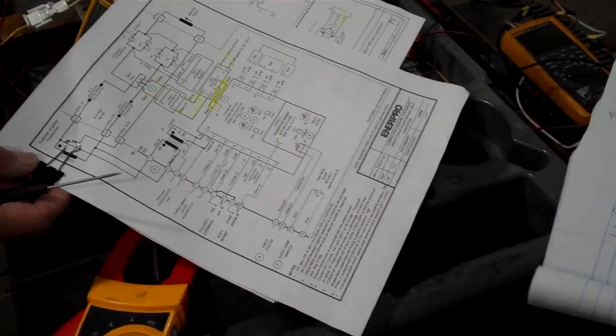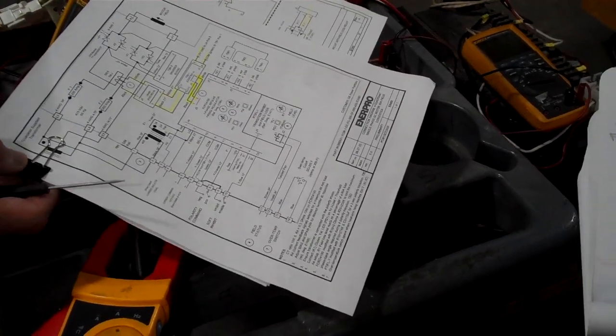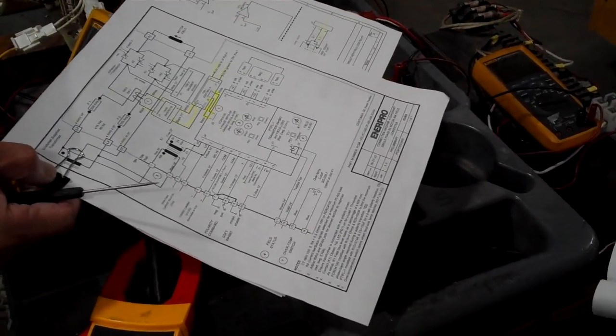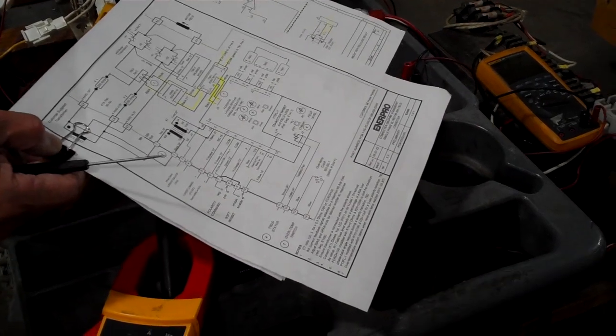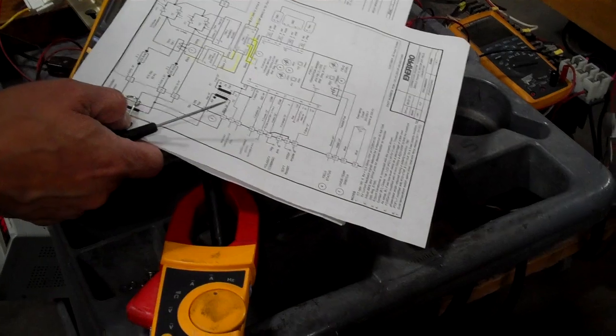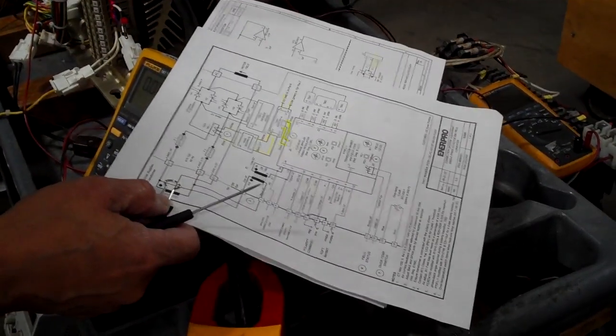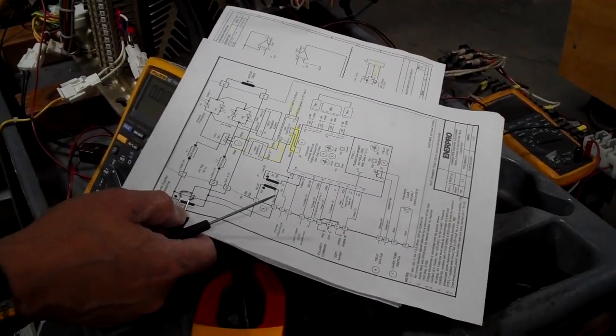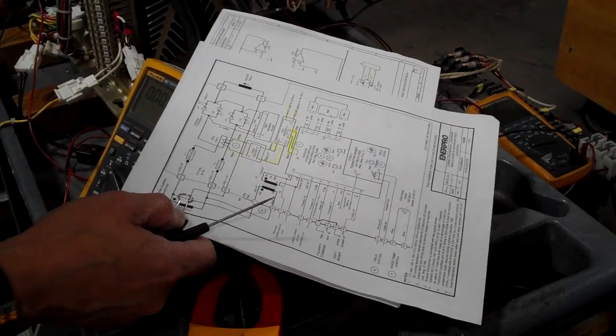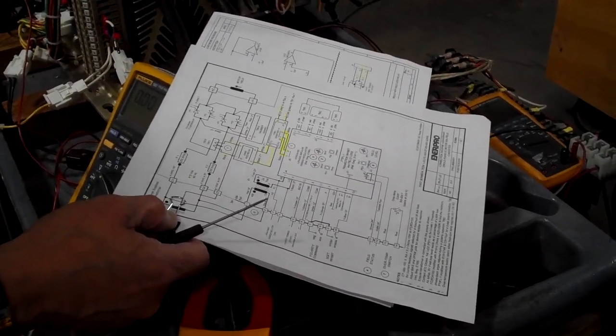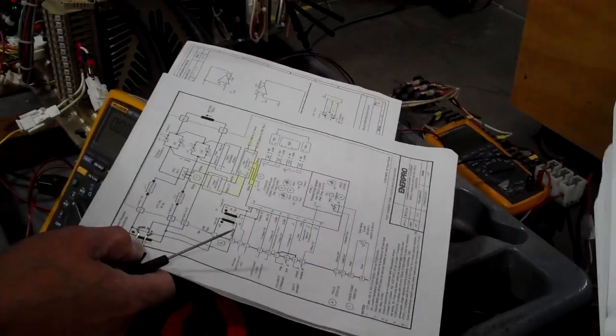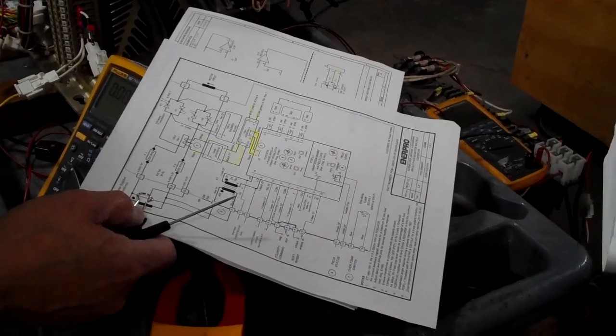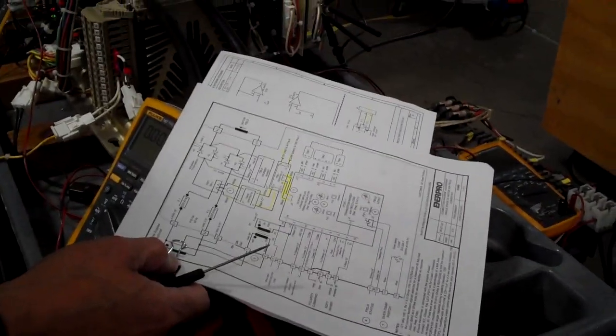In this video, we've changed our setup so that we can draw 80 amps at low voltage, high current, so we can actually see the CT providing the correct current feedback that translates into the correct field loss level, which will be compared against the field loss threshold.